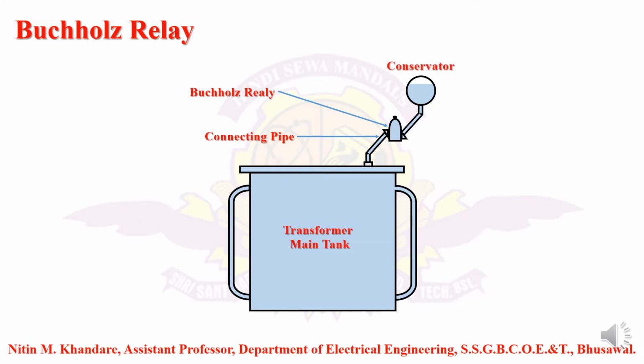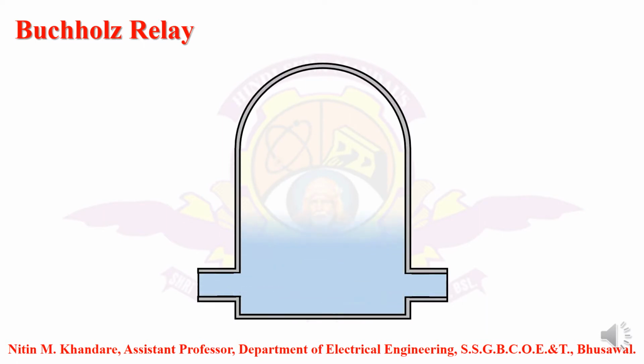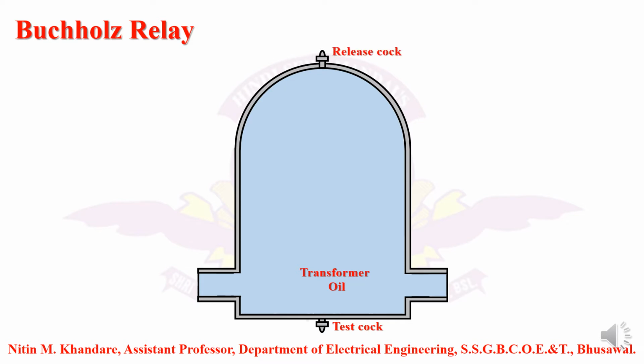Buchholz relay protects the transformer from two types of fault, that is rapid acting faults as well as the incipient faults. So we will discuss the construction of it as well as the operating principle also. So this is the Buchholz relay whose tank is always filled 100% with the transformer oil. Two outlets are there. So two cocks are provided there, one at the bottom which is called as a test cock. The test cock is utilized for testing the quality of the transformer oil. Then the second cock is provided at the top of the vessel, which is called as the release cock. The release cock is utilized for releasing the gases which are deposited during the operation of the incipient faults.